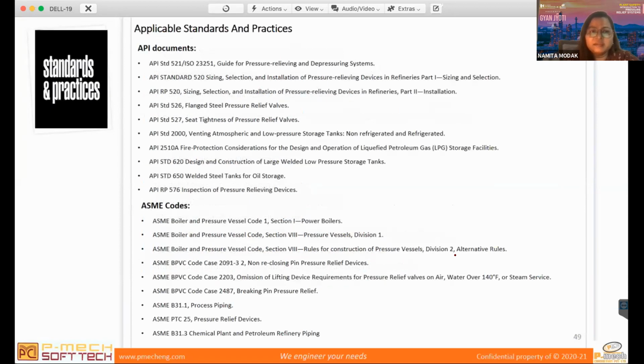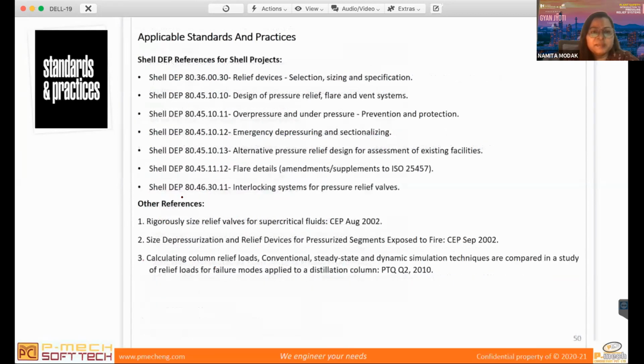These are the standards, a few of the important ones I already mentioned. So these are all API standards. Then a few are ASME. Basically, for boilers and pressure vessels, we use ASME standards. Then there are some Shell DEPs. As I said, if it is a Shell-based project, you have to refer to Shell standards and some other references. So if you refer to API 520, you will see there are different scenarios given for vapor release and liquid release. Vapor they also categorize as critical, non-critical, supercritical. In liquid, they have categorized certification required and non-certification required.